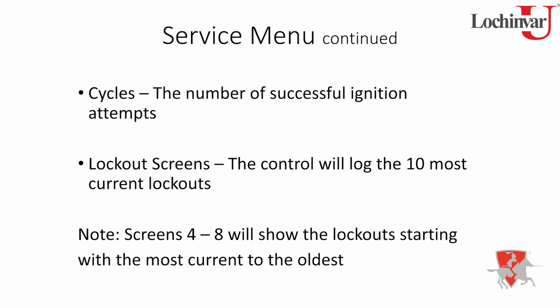Yeah, so that's a good thing to look at, what those faults are. Like Jonathan said, if it's an air pressure switch fault, then hey, you know where to go, how to set those air pressures, the deck pressure and the differential, what we're looking for. You see a flame failure, which is probably your most common. That means it didn't prove the burner flame. All right, so why didn't it prove the burner flame? Is it a gas air mixture issue? Is it a venting issue? Is it a possible flame rod issue? Right? Yeah, could be. So now we can use that information to start narrowing down our troubleshooting a little bit.